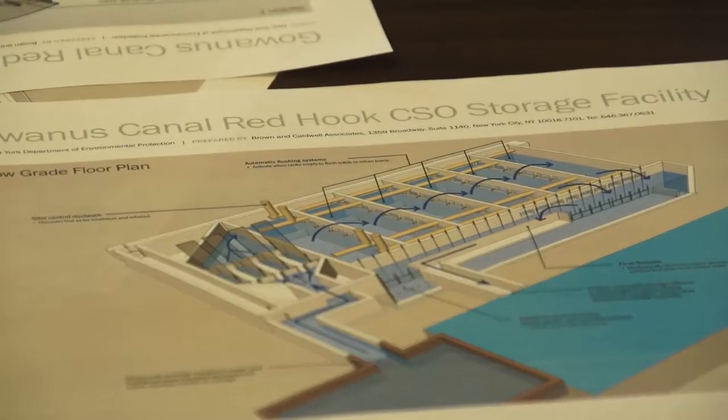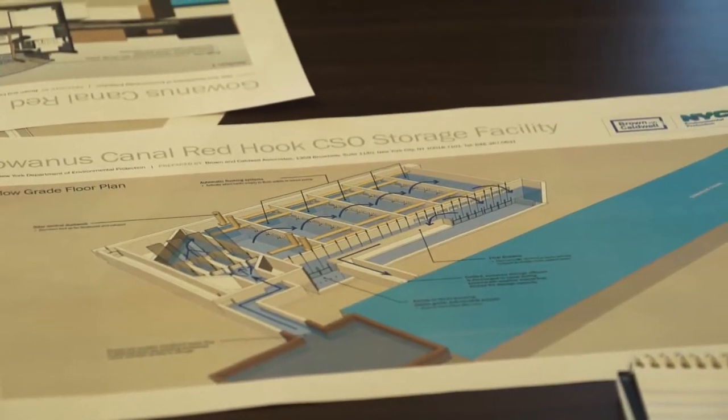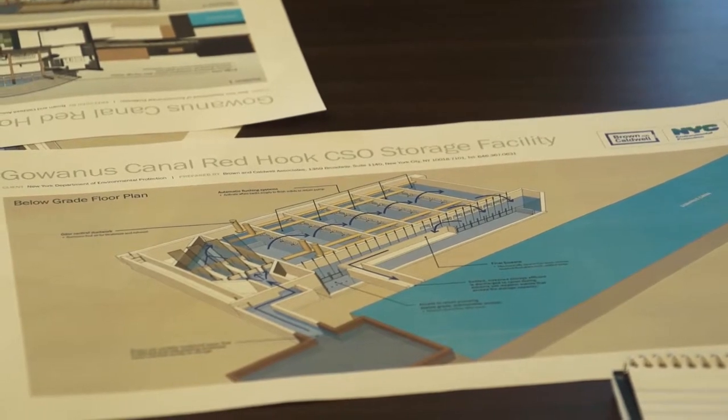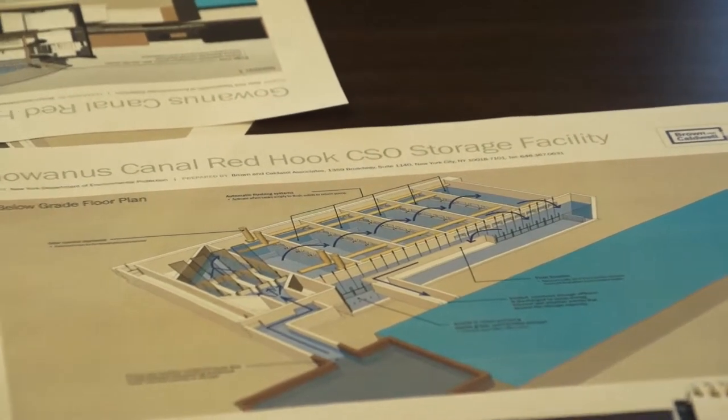So this would be the head house above the storage tanks, as you can see here. This is just a schematic. It's not a final rendering, but just gives you a look at what we're thinking. But where you see this inclined set of lines, those are bar screens. You're going to see those here at the facility.